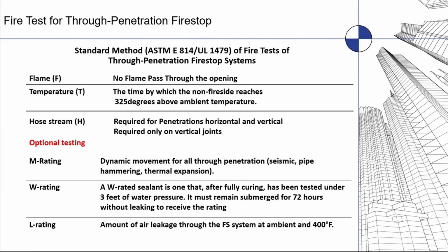Another one that is conducted in fire stopping, in penetrations, the horizontal and vertical items, is that they are exposed to a hose stream test. So they shoot it with a fire hose. You'll see a good example of this as we go along. They shoot it with a fire hose on the hot side of the furnace after they've burned it for whatever time duration. And if there's no visible water on the face side, the cold side, then it has passed the hose stream test. And on the joint applications, which would be perimeter joints or expansion joints or control joints or whatever those kinds of joints are, the hose stream is only conducted on the vertical joints themselves. It is not conducted on the horizontal joints.